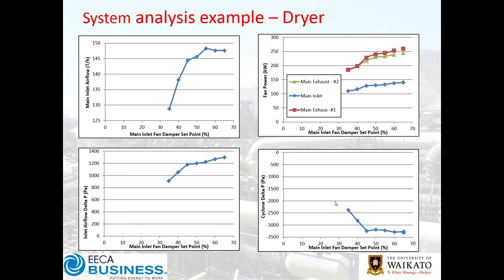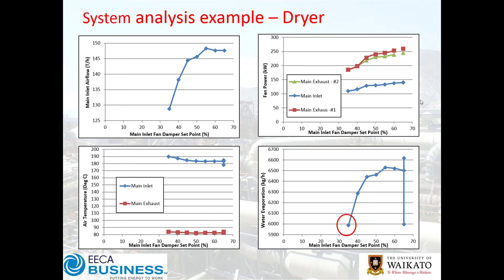Below is the inlet airflow delta P — the change in pressure drop. You can see it's sort of a parabola but with a very flat section at the top, and perhaps going the other way to what you'd ordinarily expect — a downwardly sloping curve. A similar effect appeared on the cyclone on the exhaust side — negative pressures, relatively flat, then reduced. This is where we developed the system curves of what was going on and did some trials.